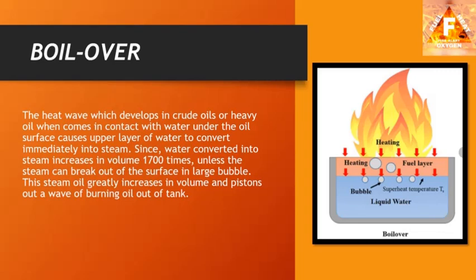Here you can see a tank with fuel on fire and water present beneath the fuel. What happens is that due to the continuous burning of fuel, the heat layer travels to the surface of the water. Due to the heat, the water starts converting into steam, and it is a property of water that when it converts into steam it increases its volume by 1700 times. This sudden eruption ejects the whole of the tank contents and produces a dangerous shower of burning liquid radiated over the immediate area, and this is how a boil over phenomenon occurs.